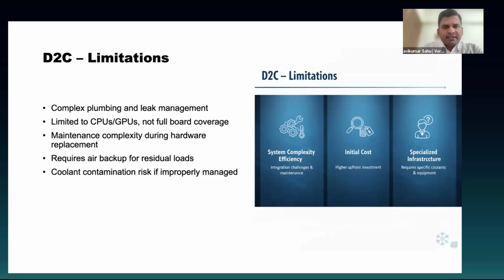Limitations. As we said, it has a rack manifold and row manifold, which are critical from a design perspective. If the design is not proper, then it will not work, and leakage chances are much higher. Second, for the CPU, it means you still require an air cooled component. So you have to make provisions for either a fan wall, indoor cooling units, or an RDHx. That is an additional thing. From a maintenance perspective, it is a little bigger challenge, and coolant contamination is also some kind of risk involved here.